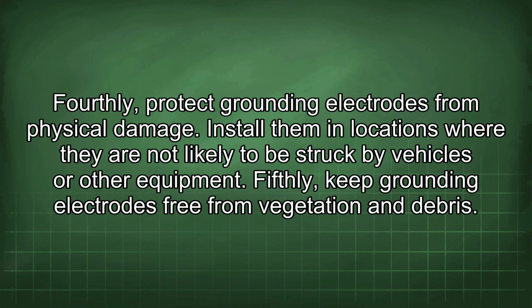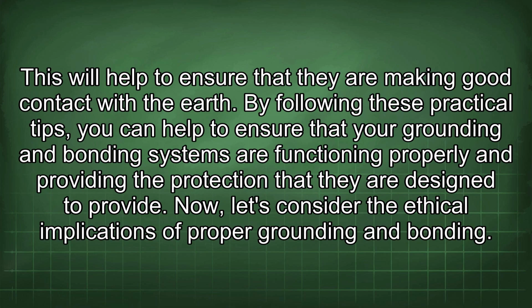Fourthly, protect grounding electrodes from physical damage. Install them in locations where they are not likely to be struck by vehicles or other equipment. Fifthly, keep grounding electrodes free from vegetation and debris. This will help to ensure that they are making good contact with the earth. By following these practical tips, you can help to ensure that your grounding and bonding systems are functioning properly and providing the protection that they are designed to provide.